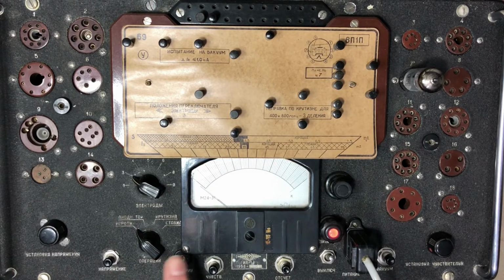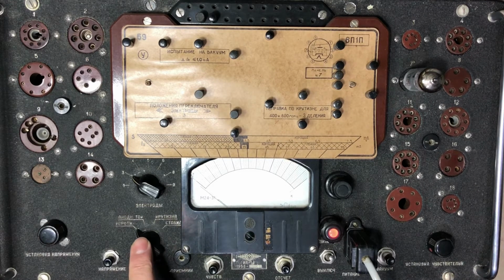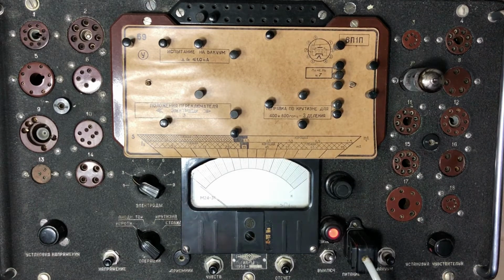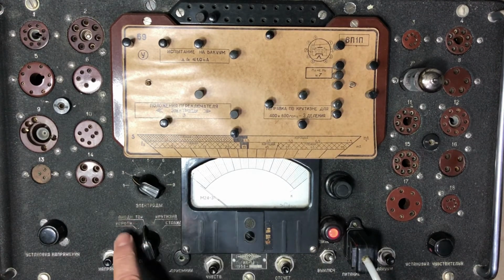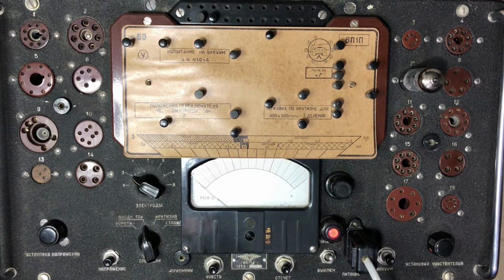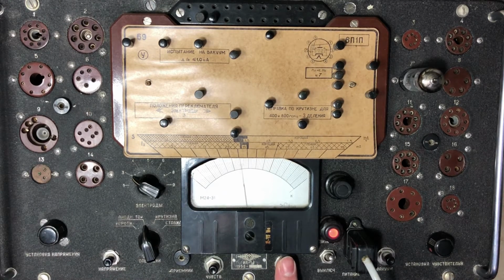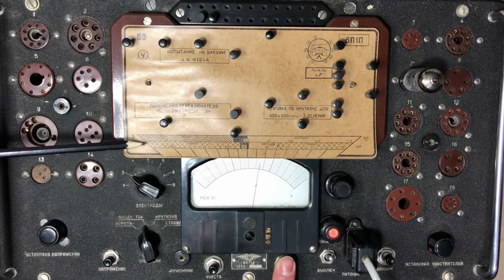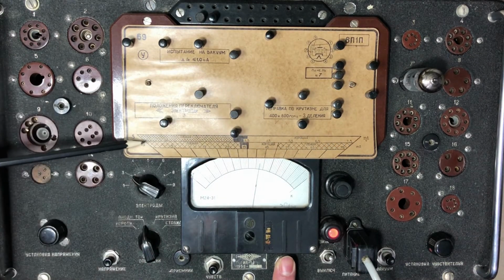So we have another two push buttons. This is for test, measure, and this is for calibrating the slope, steepness, amplification, milliamps per volt. In this position, leakage current on 3, push that button, nothing. Tube is okay, no leakage. Next position, anode toka. That means plate current. To see the plate current, push this button. This is the range for plate current.